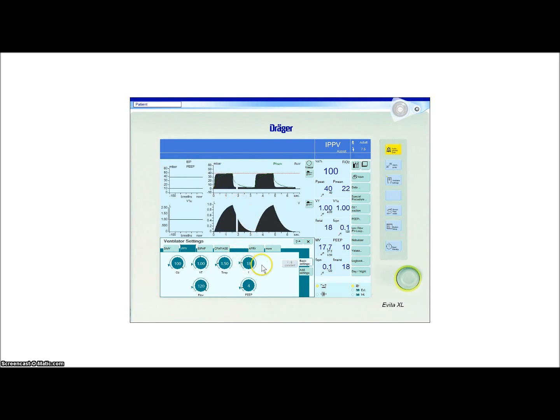I could decrease the inspiratory time and you would see this waveform that wouldn't linger so long. Go ahead and do that, and watch this waveform. It's a lot shorter. Now if I increase the inspiratory time to 3 seconds, this plateau is going to be a lot longer. But I don't want to fool around with that too much. I want to keep him on 1.5. So here we are. It is giving him a tidal volume every 3 seconds or so.